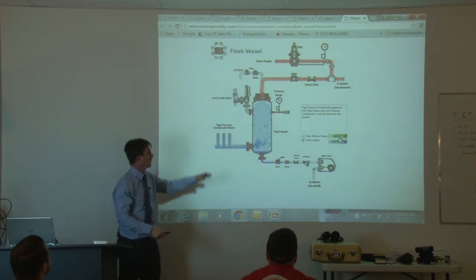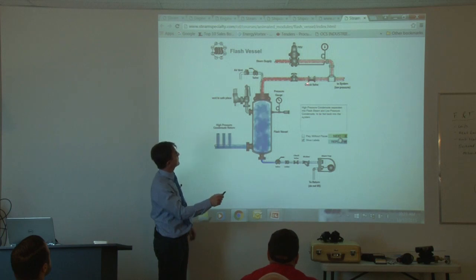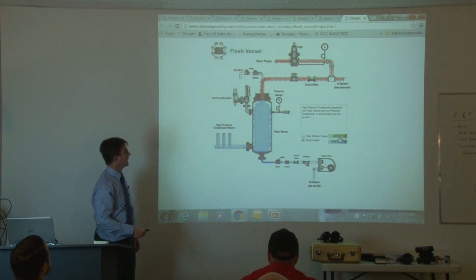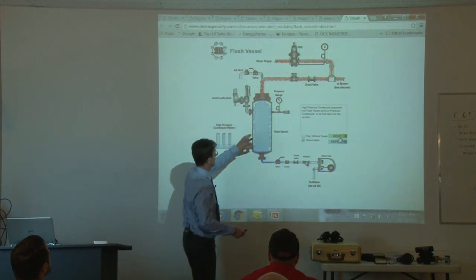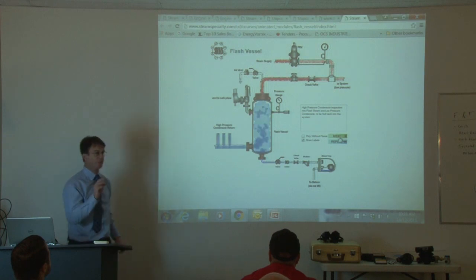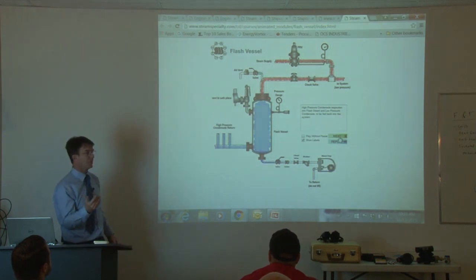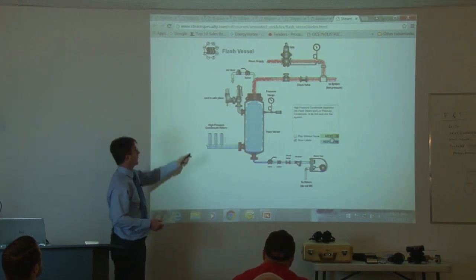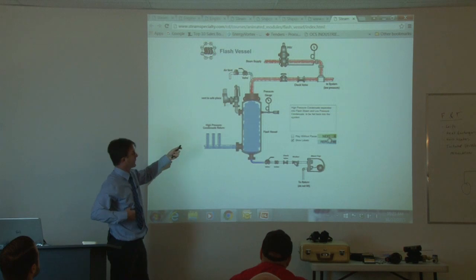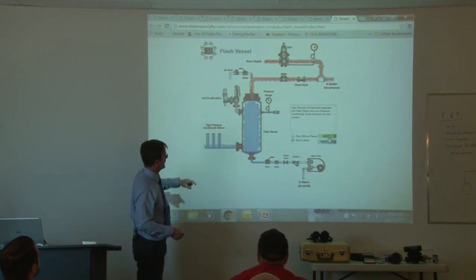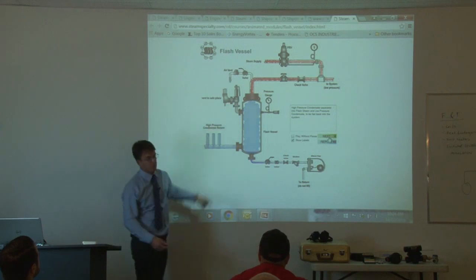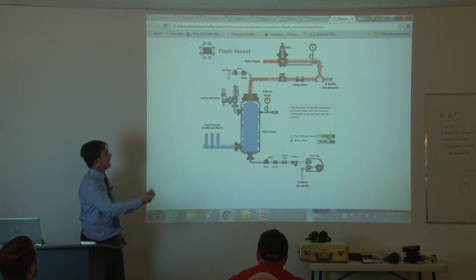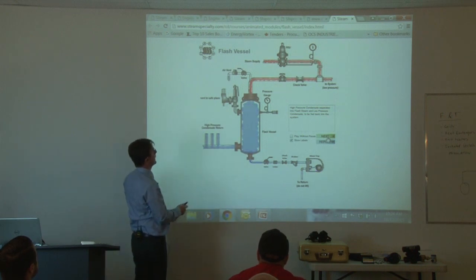But if we drop in the amount of flash steam feeding the low pressure system, then that PRV opens up and starts supplying plant steam. A lot of times what we'll do is put in a back pressure valve — a back pressure valve is simply a reverse-acting PRV, acts very much like a safety valve. But you don't want your safety valve popping all the time because that wears it out and it'll start chattering and leaking by. So instead of using your safety valve, add in a back pressure valve, set to slightly below the required pressure, which vents off excess flash steam when we don't have a use for it.